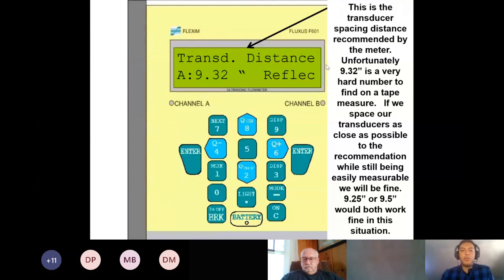This is where it recommends the transducer spacing distance. We want folks to get as close to that number as possible. We know that with a crude measuring tape, 9.32 can be a little tricky to get for your spacing. So there is another menu after this where you can actually tell it what you put. So instead of 9.32, maybe just do 9.3 or 9.25, and then you can tell the meter that that's what your spacing was instead of the 9.32. On this menu, we also see that it's a reflect mount. So just in case you were wondering how you wanted to mount it with your sound path, this will tell you right in this menu.